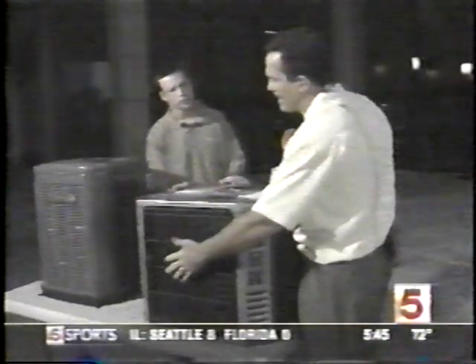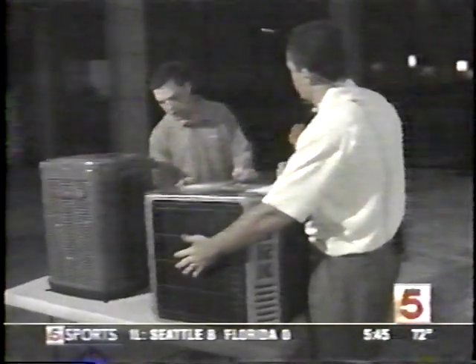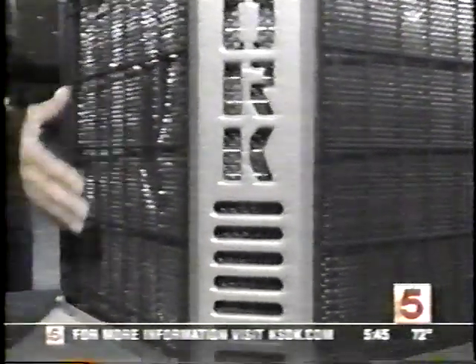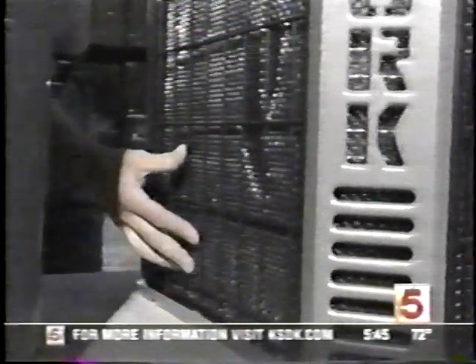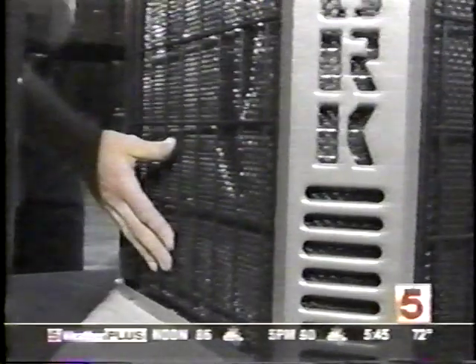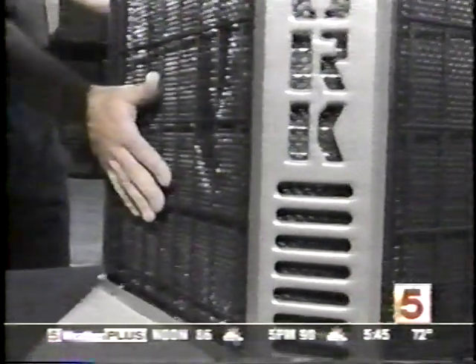Why is it important to keep these coils up here free of debris? The unit is cooled by air, and the fan rejects the heat out the top. So the air is brought in through the side of the condensing coil, cooling the system, and then rejected out of the top. So if it has an impede of airflow, it's not going to give you the performance you need. What are some of the symptoms then if you know you're having some problems? First off, like I said, would be the set point of the temperature is not correct in the thermostat. So you want to come outside and make sure the unit is running.